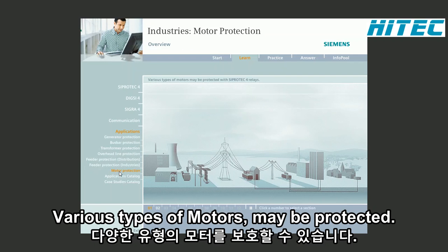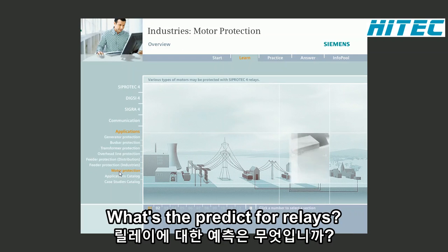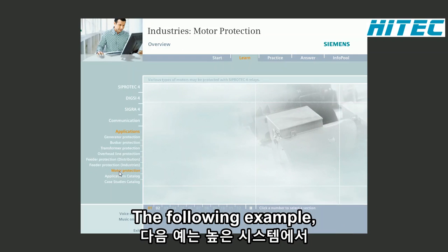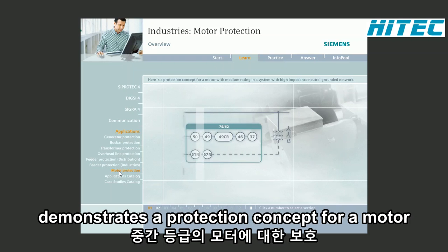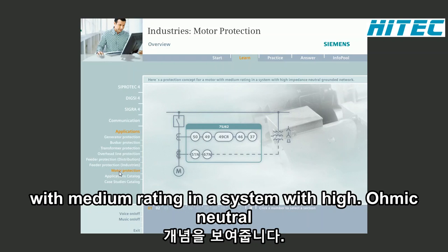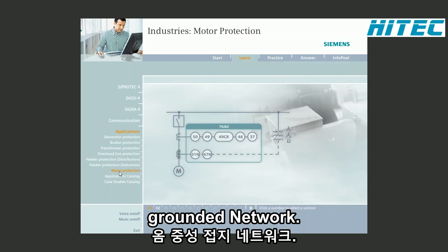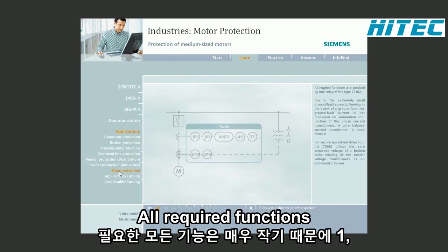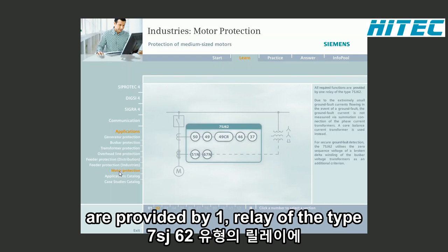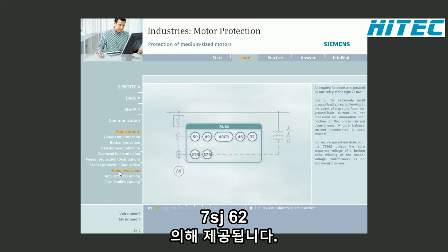Various types of motors may be protected with SIPROTEC 4 relays. The following example demonstrates a protection concept for a motor with medium rating in a system with high ohmic neutral grounded network. All required functions are provided by one relay of the type 7SJ62.